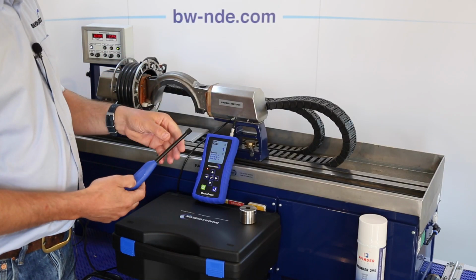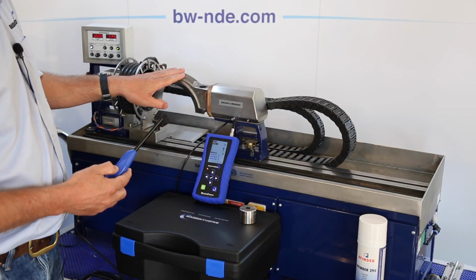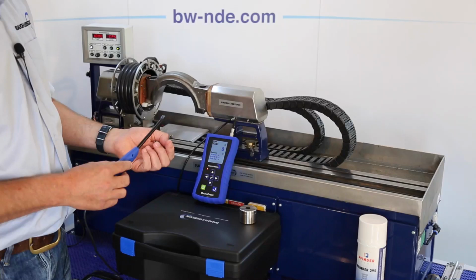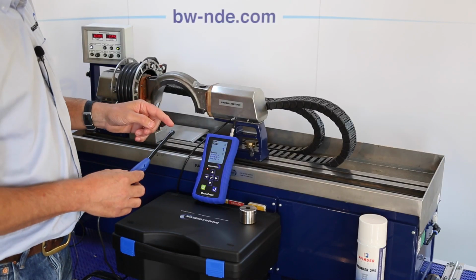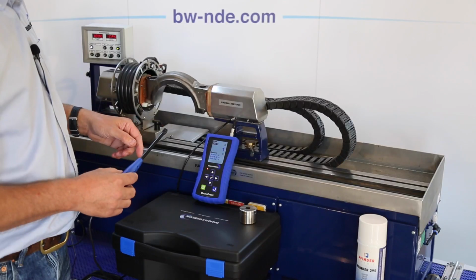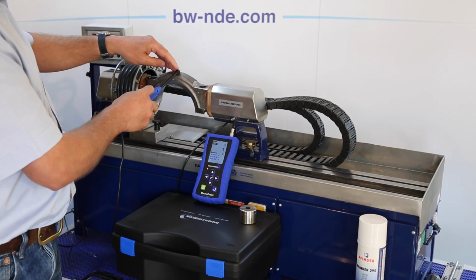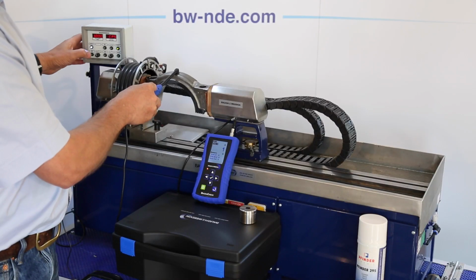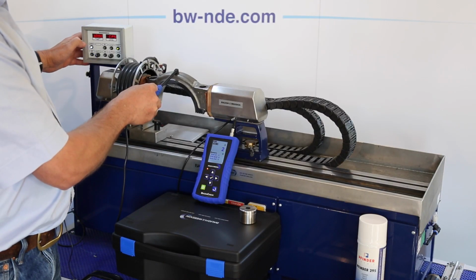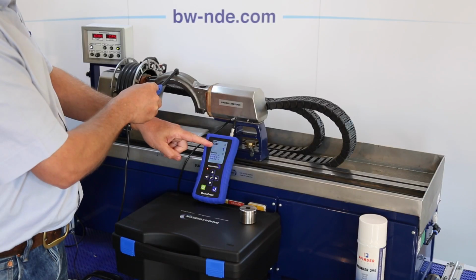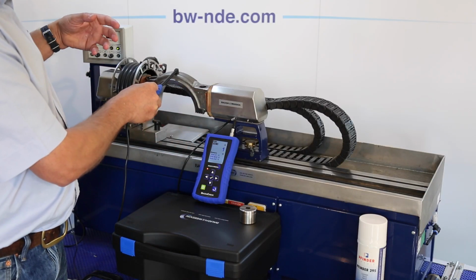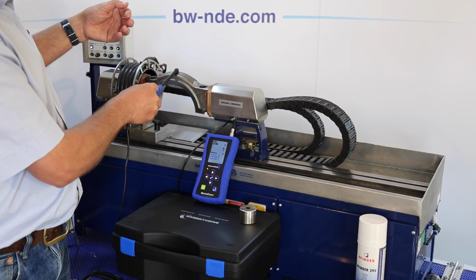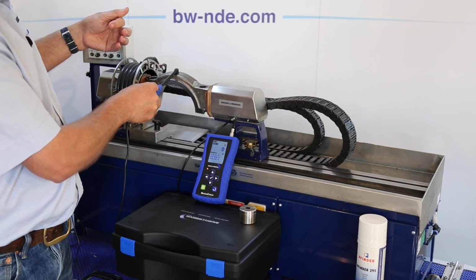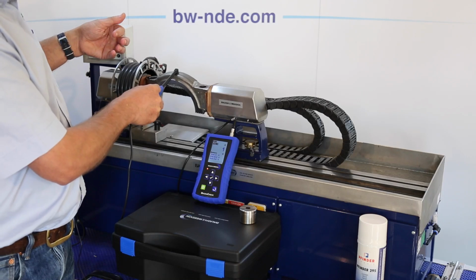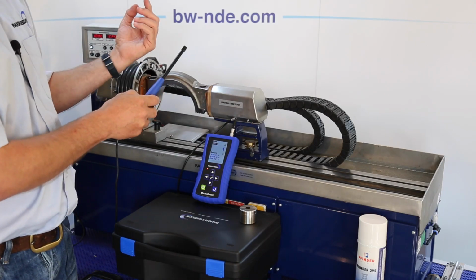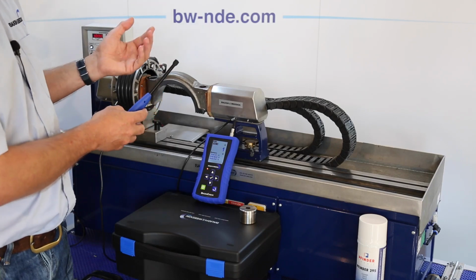So what we've done in this case is we've chosen to put face C onto the surface of the component. It will then ignore any fields coming out through face C and only read face A and faces D to E. So put the probe onto the surface, face C, magnetise the part, and as you can see we get a combined reading in the top window, which is a combination of fields through face A and fields through faces D to E, and those are the ones we're really interested in. It's ignoring any fields coming out to the surface which would hamper our inspection or are not of interest to us.